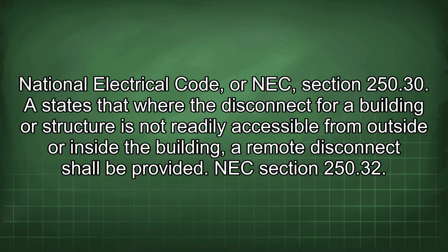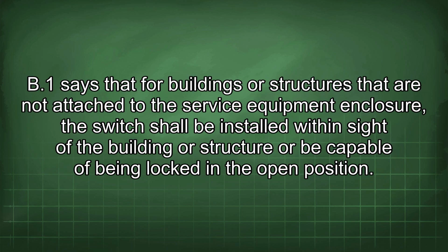National Electrical Code, or NEC, Section 250.30, states that where the disconnect for a building or structure is not readily accessible from outside or inside the building, a remote disconnect shall be provided. NEC Section 250.32(B)(1) says that for buildings or structures that are not attached to the service equipment enclosure, the switch shall be installed within sight of the building or structure or be capable of being locked in the open position.